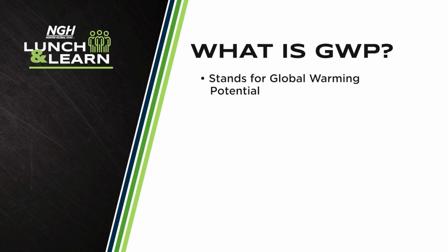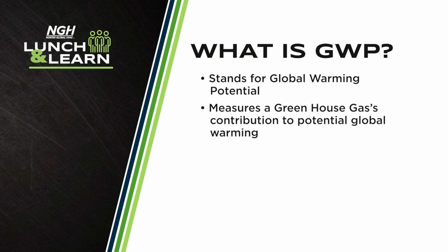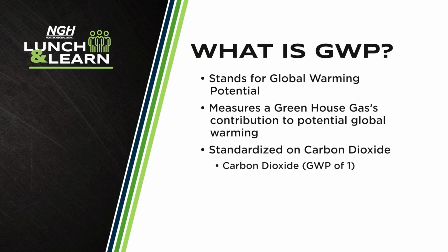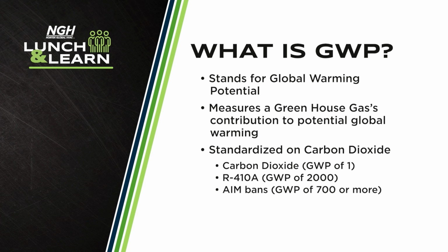GWP stands for Global Warming Potential, and it's how we measure a greenhouse gas's contribution to potential global warming. A greenhouse gas absorbs energy from the sun and traps it in the atmosphere. GWP is standardized on carbon dioxide, the gas we breathe out when we exhale. Carbon dioxide has a GWP of 1. R410A, which has been in wide use for over 20 years, has a GWP around 2,000, meaning it traps 2,000 times more energy in the atmosphere than carbon dioxide. Since that's well north of the 700 benchmark, we knew we had to make a change.